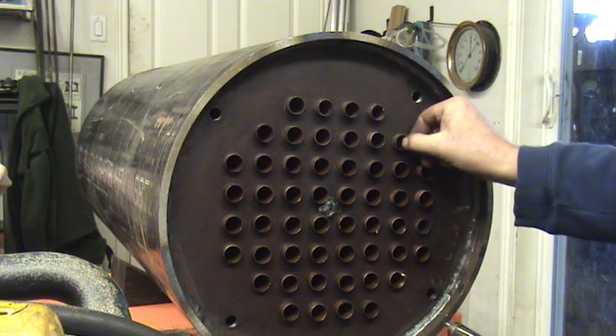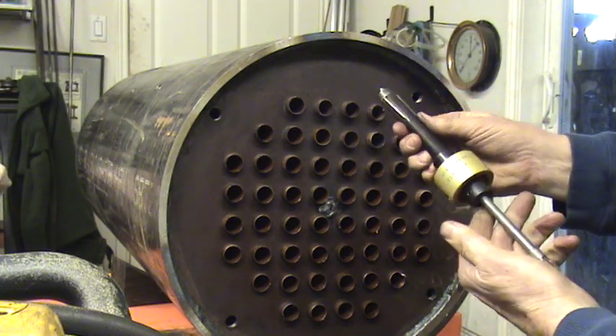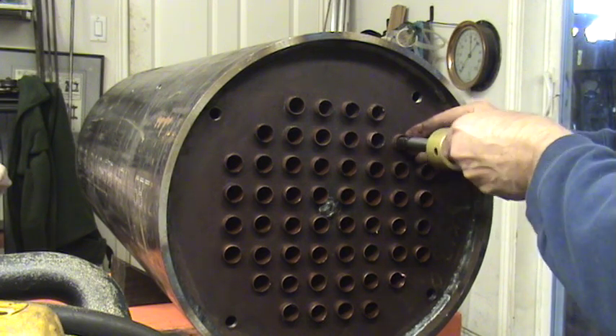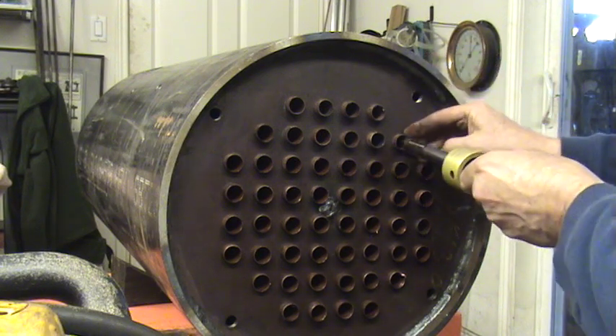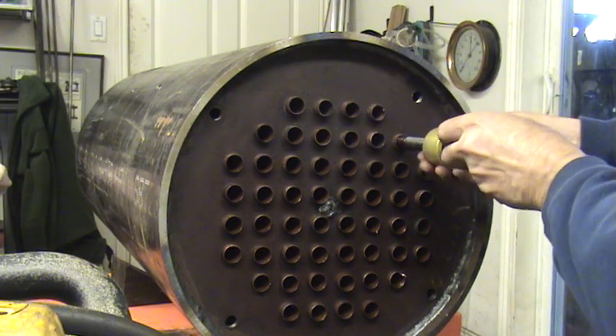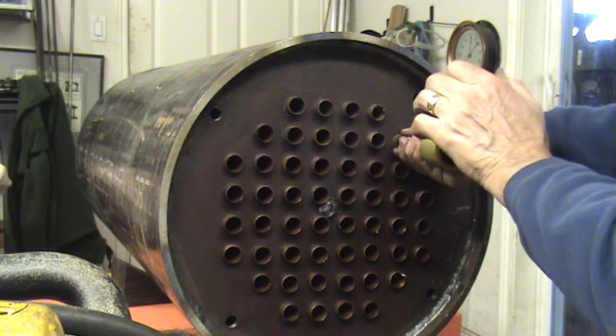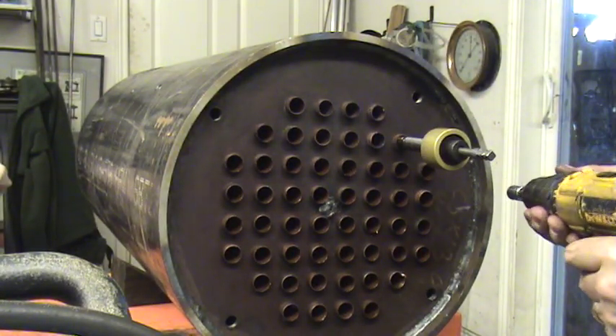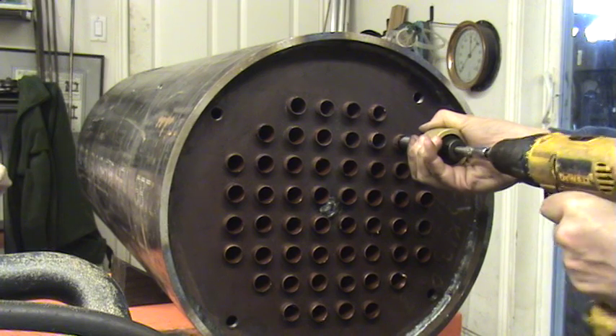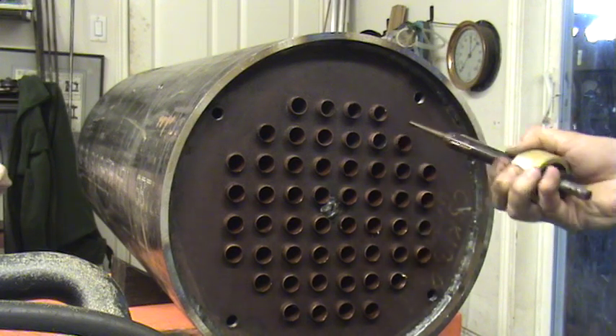The tube is loose in there right now because I haven't rolled in the other end of it. I pull the part back and just kind of hold the tube. I put oil on this too — they want you to put oil on it when you roll it in; it's the manufacturer's recommendation. I put it in about halfway and then just gently push the center of it in with the heel of my hand, and roll it in. I'm pushing in with the heel, then reverse it and pull it out. Of course the other end has to be done as well.